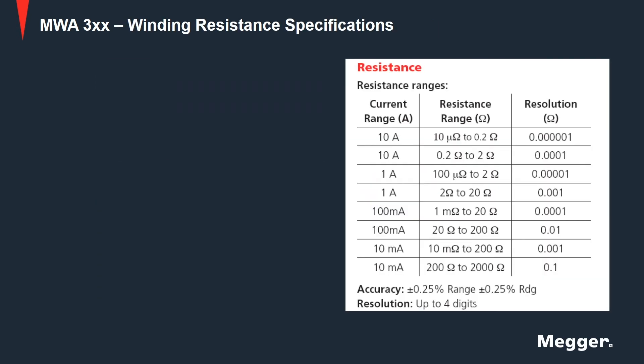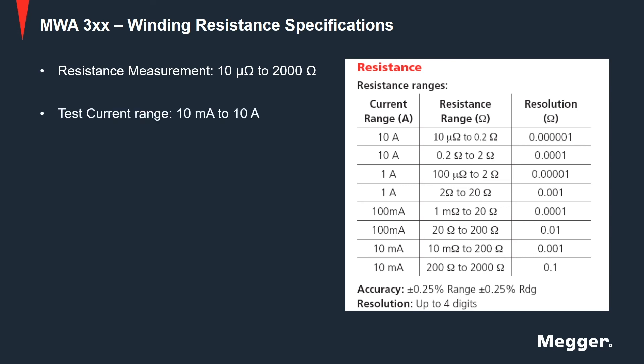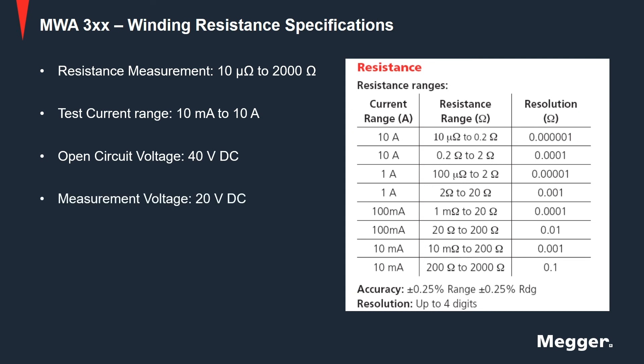Looking at the winding resistance specifications, the MWA has a resistance measurement range of 10 micro ohms to 2000 ohms, a test current range from 10 milliamps to 10 amps, an open circuit voltage of 40 volts DC, and a measurement voltage of 20 volts DC.